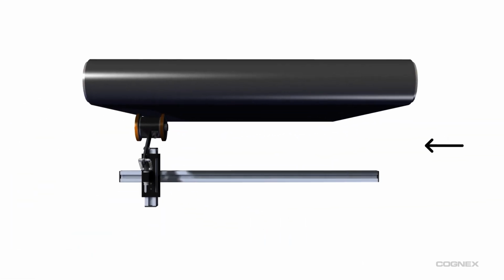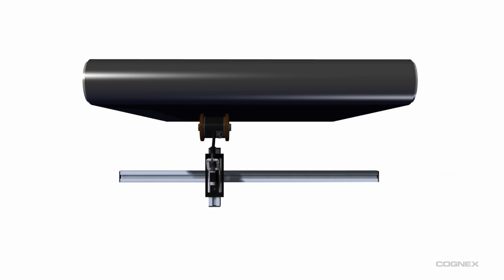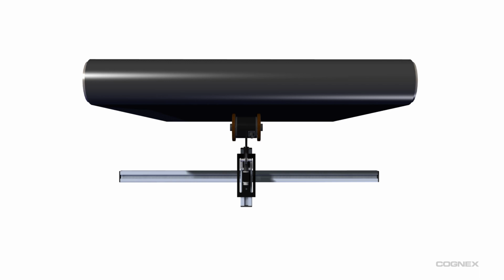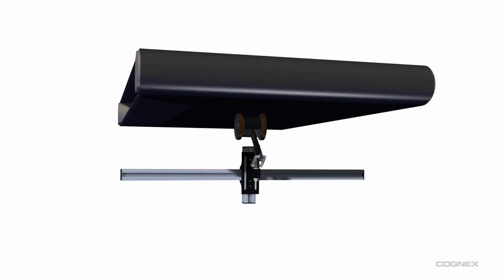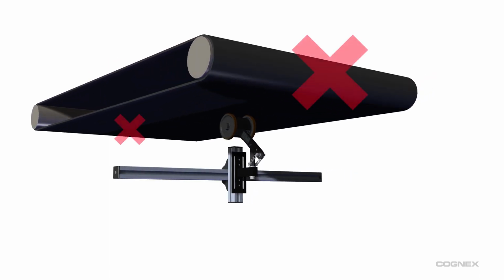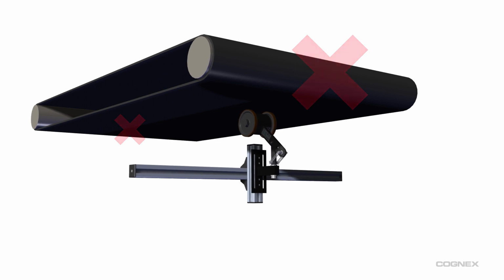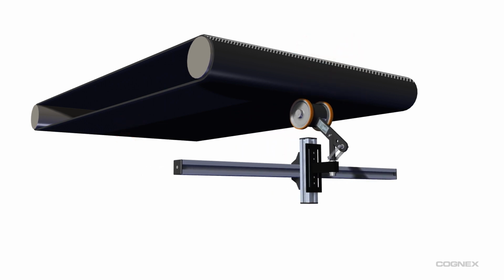There needs to be a clear space under the belt and a beam must be present for mounting. Ideally, the encoder should be mounted in the center of the belt to avoid worn and frayed edges. Along with placing the encoder at the center of the belt, whenever possible, do not mount the encoder on belt rollers. It is acceptable only as a final option, as long as the encoder is made to not bounce when coming in contact with the belt seam.